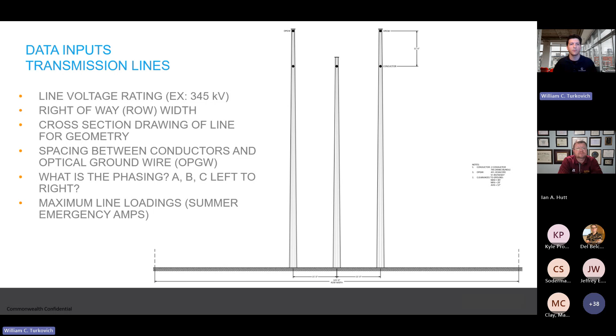The next is probably the most difficult to gather: the maximum line loadings. This is the amount of current going through those lines at any moment, and the highest value of them all. An example would be the summer emergency rating, meaning everyone has their AC on in the summer and all the transmission lines are maybe overloaded for a certain degree of time. That might be the worst one, or the winter might also be worse. So you have to look at all of them and figure out which one is the maximum, because the higher the current going through the lines, the higher the magnetic field.